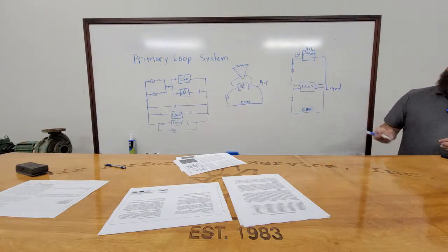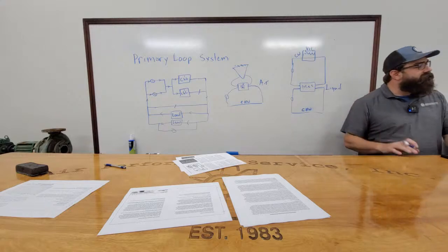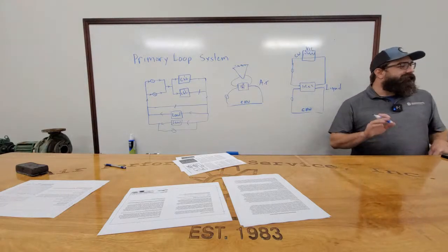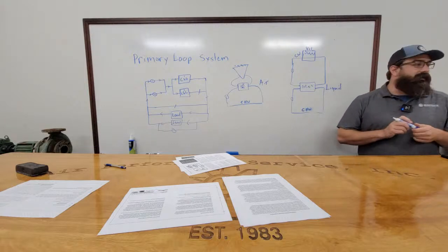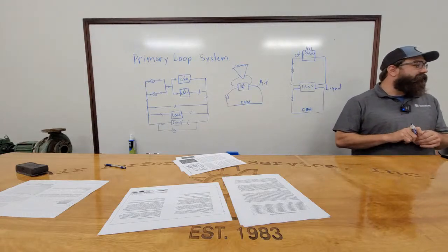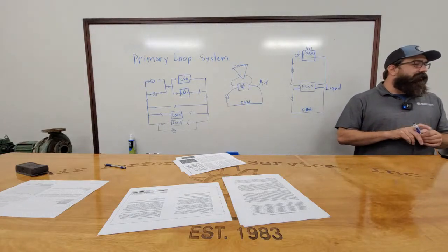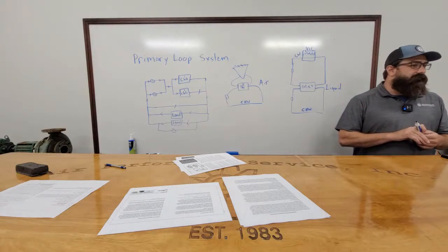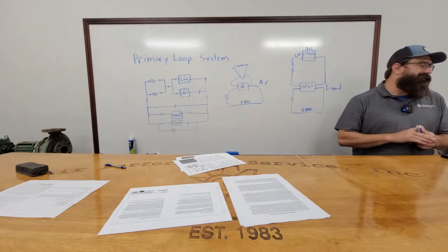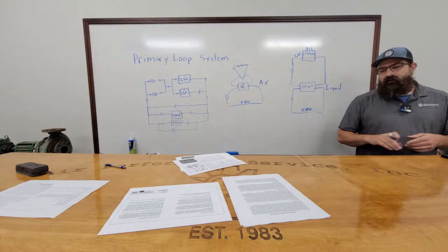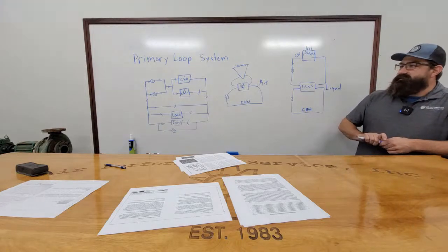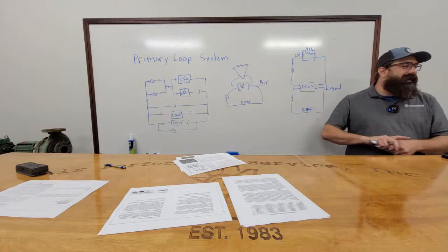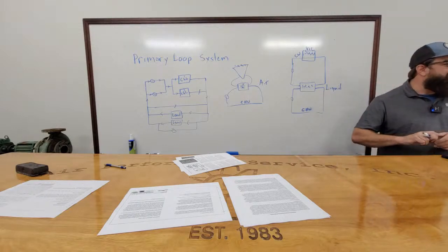There are a couple of different kinds of condenser water systems. We won't really go into those because I don't know that much about them. But basically, most of them are going to be constant volume, constant flow type setups. There are a few that will actually maintain flow set with a VFD, but most of them are just on off. Typical condenser water system's going to run like 75 to 85 degrees, depending on the equipment.